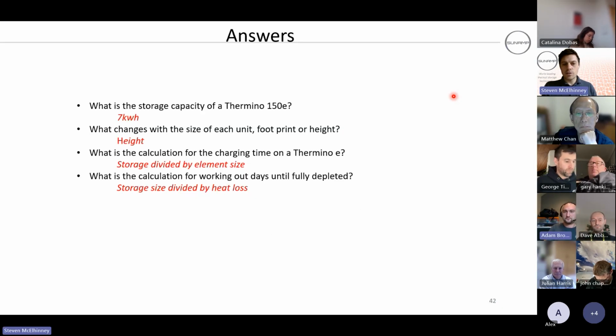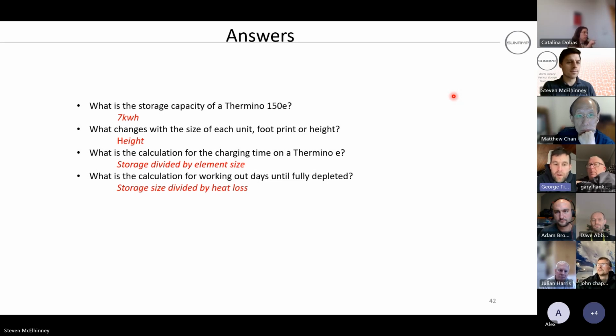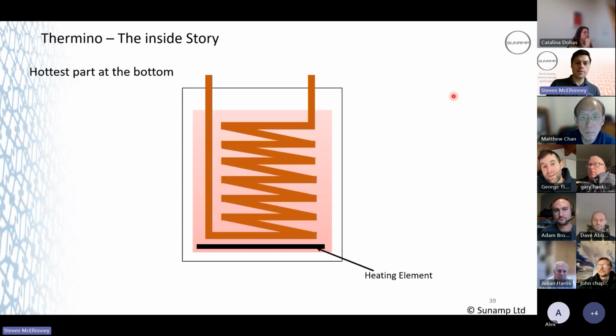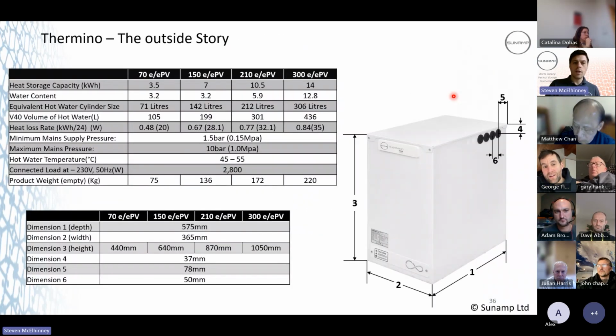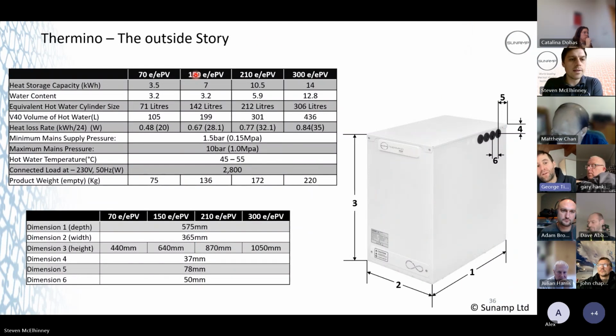Has anyone got any questions on that bit so far? Obviously, storage capacity, you've listed it at 40-degree outlet. So a 30-degree delta between 10-degree cold in, 40-degree out. Obviously, at 55-degree outlet, that pushes that delta to 45. So it's reducing the capacity. So, for example, the 300 at 55 is what, about 260-ish litres?